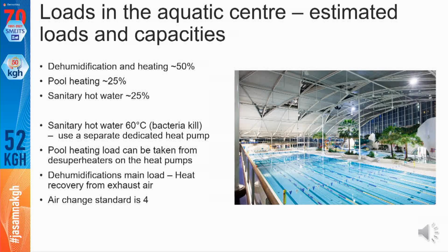The sanitary hot water in Denmark needs to be 60 degrees. I know in Norway they need about 65 degrees, and in other countries a little bit lower. So you have to check locally what is required for bacteria kill. I don't know if there's a difference between the bacteria, or if it's tolerance to the bacteria, but that is something that can be looked into more.